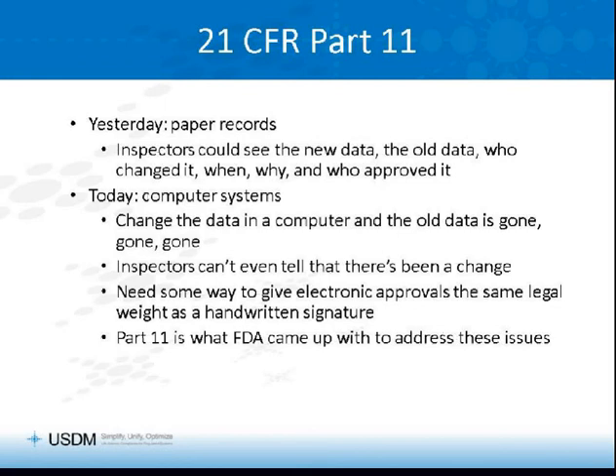The whole point of Part 11 is so that inspectors can inspect your records even though they're on computers. When they were on paper, inspectors could see everything: a single line through an old value, a new value, initial and date, and typically a reason why it changed.